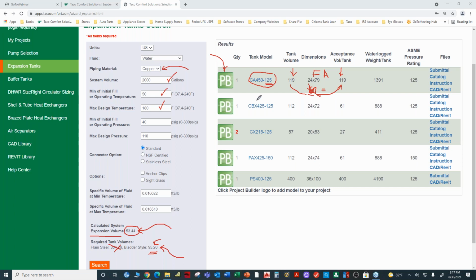The second selection is a CBX. Also, in this case, it's 425 liters instead of 450. So the tank volume, the steel container, is 112. Again, that's greater than the 95. But the acceptance volume is only 61. Well, the acceptance volume of the bladder has to be greater than the expansion. It is in this case. It's 61. The fluid is expanding 53.44. So that will also do the job. Let me put a check mark here. So obviously all of these will do the job.